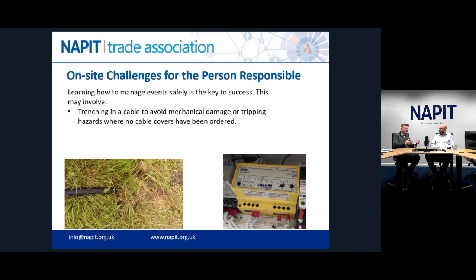But one of the key aspects about trenching cables in like that is that you know where they are. And so it's a relatively controlled environment, unlike a cable that's buried under the road, for example, where people will long forget where it was actually buried. So an environment like that's there for a short duration. So the cable just has to be sufficiently mechanically protected. And so also hence the reason for the rubber cable, because it has better mechanical protection. Good.